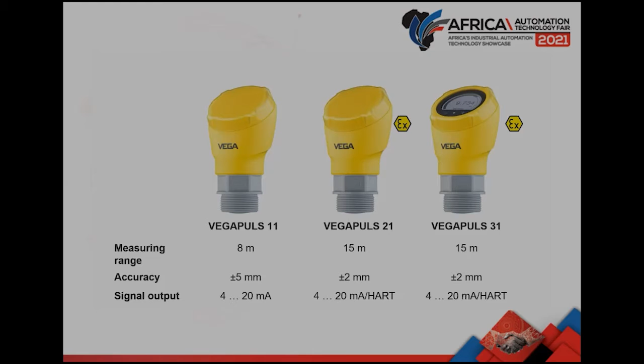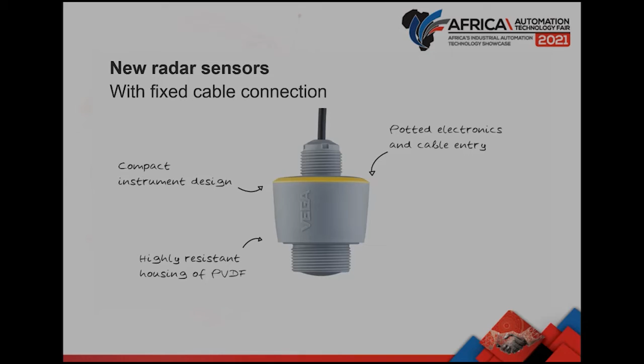Then the cable option. So we have a compact radar with a direct cable outlet, and this is also designed for connection directly to a PLC. It's 2-wire loop powered. It can also be connected to these controllers that we have on offer. And the potted housing is completely sealed, so we have a high IP rating on this device. So even when flooding occurs, for example, if the position of mounting is low enough where you might have an overflow situation, the device will not drown, if I may say so, and as soon as the level drops again, the device will continue functioning as normal.